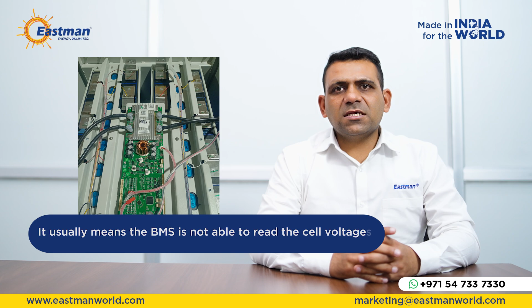Today we will talk about how to resolve AFE sample fault or communication failure error. AFE fault is analog front end sample fault. Whenever you see AFE sample fault or communication failure error, it usually means the BMS is not able to read the cell voltages or communicate properly with its internal board or external devices such as inverter and charger.